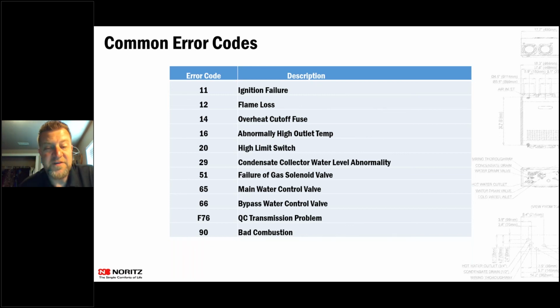F76 is a quick connect transmission problem, which just means you have two units with the cables connected, but for some reason they can't talk to one another. A lot of times something's wrong with the cable or it wasn't connected properly. With those quick connect cables, it connects to the unit, but there's also a ground wire that grounds to the ground board. If you don't put those grounds on there, you'll get that 76 code.